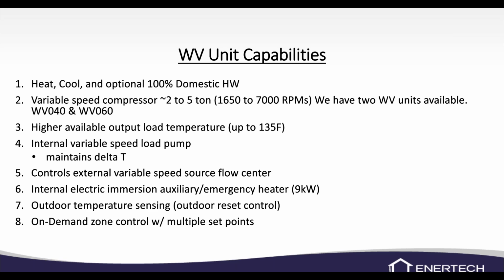There is a connection that will control the external variable speed source flow center, and basically it monitors temperature difference as well on the source side. There's an internal electric immersion heater, and it's used for auxiliary or emergency heat, and it is a 2-stage 9-kilowatt heater. So the first stage of that heater would be 4.5 kW, and the second would be the other 4.5 kW.